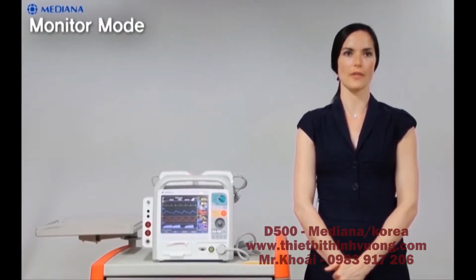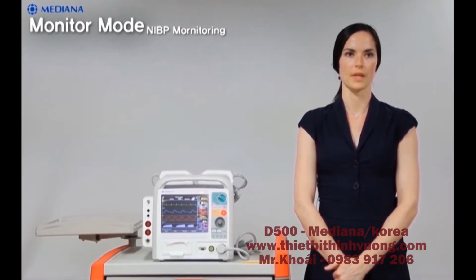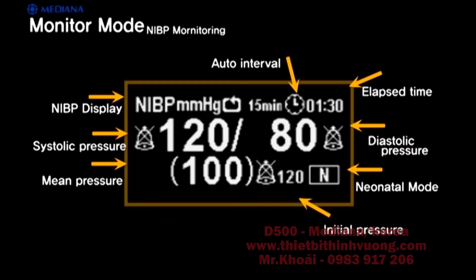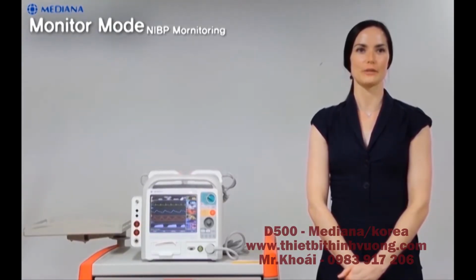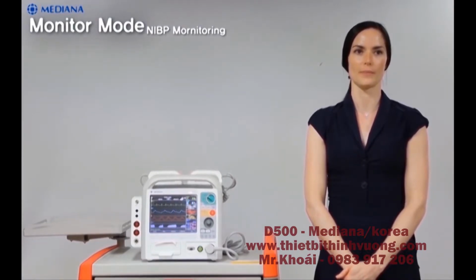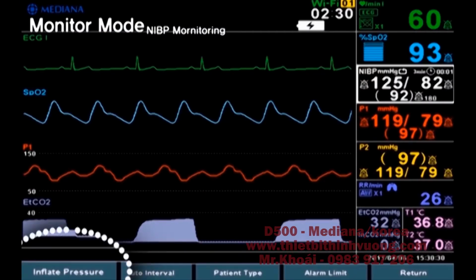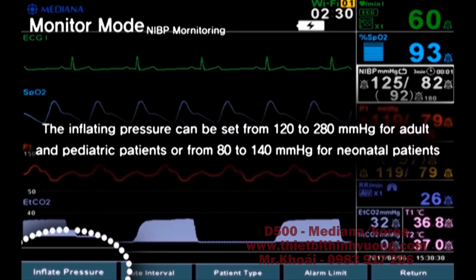Now let's continue with NIBP monitoring. Here you can see how to check the NIBP display measurements. Let's take a closer look at the NIBP menu. Number 1, inflate pressure. The inflating pressure can be set from 120 to 280 millimeters of mercury for adult and pediatric patients, or from 80 to 140 millimeters of mercury for neonatal patients.